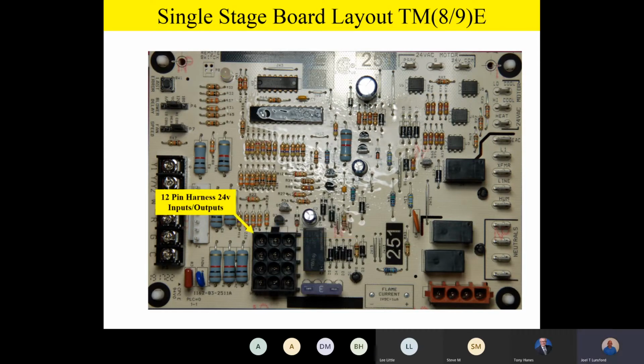Next to that, we have a 12-pin harness. This 12-pin harness is where we have our 24 volt inputs and outputs. The things that would be plugged into that 12-pin harness would be things like your gas valve, your pressure switches, your flame sensor, and all that's going to be plugged in there.